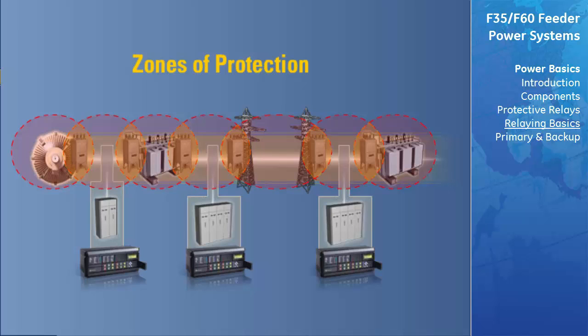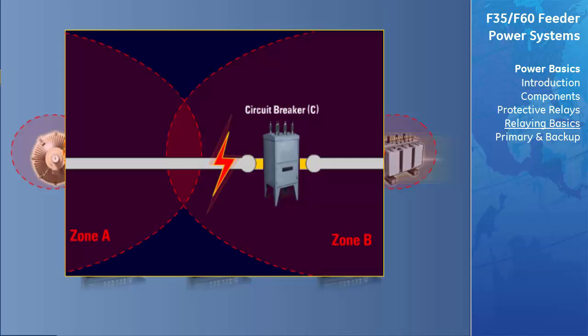The preferred practice is that adjacent protective zones overlap around the circuit breaker so that for failures anywhere other than in the region of overlap, the minimum number of circuit breakers will be tripped. If zones are set up such that overlap occurs on only one side of the breaker, the relaying equipment of the overlapping zone must also be able to trip breakers of the neighboring zone. For a fault located as shown, the circuit breakers of zone A will trip, but because the fault is outside zone B, the relaying equipment of zone B will need to send a trip signal to the breaker in zone A.